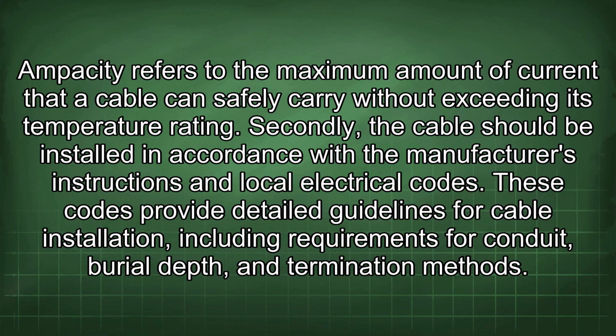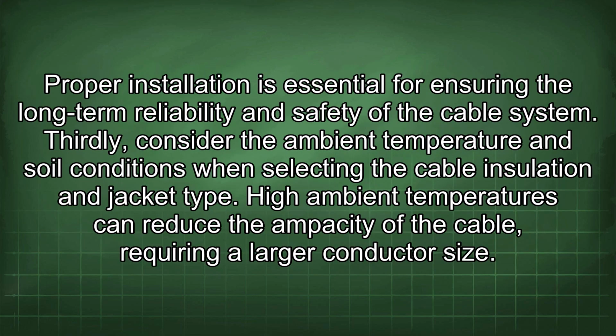Secondly, the cable should be installed in accordance with the manufacturer's instructions and local electrical codes. These codes provide detailed guidelines for cable installation, including requirements for conduit, burial depth, and termination methods. Proper installation is essential for ensuring the long-term reliability and safety of the cable system.